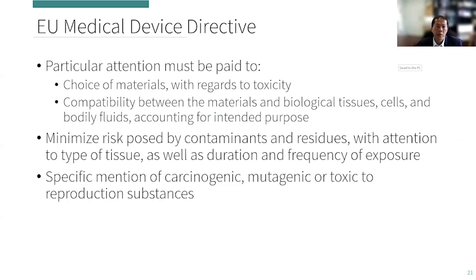If we look at the EU Medical Device Directive, they don't actually explicitly mention biocompatibility, but they do call out that particular attention must be paid to the materials as far as the choice of materials and the toxicity of the material, and that there should be compatibility between the materials and biological tissues, cells, and bodily fluids.